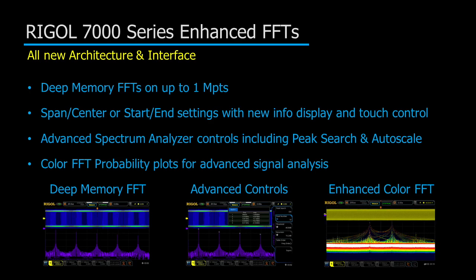RIGOL's 7000 series oscilloscopes enhance the way engineers analyze frequency domain information in three important ways. First, the 7000 provides FFTs that utilize the deep memory of the scope up to 1 million points. This makes for more complete and accurate frequency analysis of high speed and RF signals.